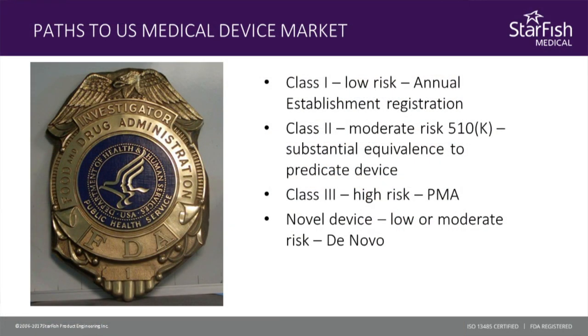So I will just step back and give a little introduction to the FDA. As you know, the FDA quality system regulations recognize several classifications. You can be a class 1 device, which is low risk, and in general, you just need to register with the FDA, which is very low cost. Then you have class 2 devices, and this is what most people are working with. They are moderate risk, and you're going through the 510K process. When you're doing the 510K, you are technically proving that your device is substantially equivalent to a device that is already on the market.